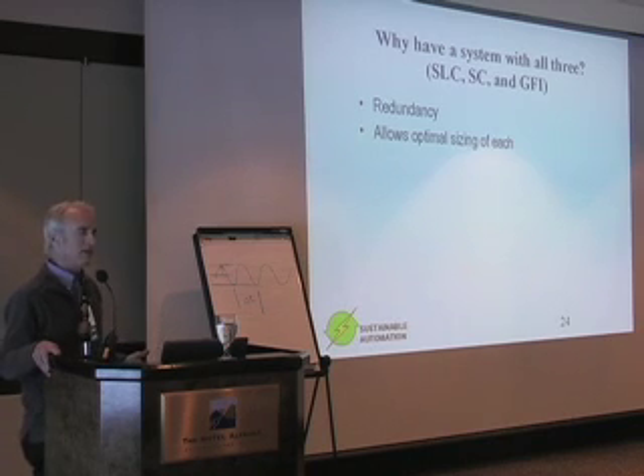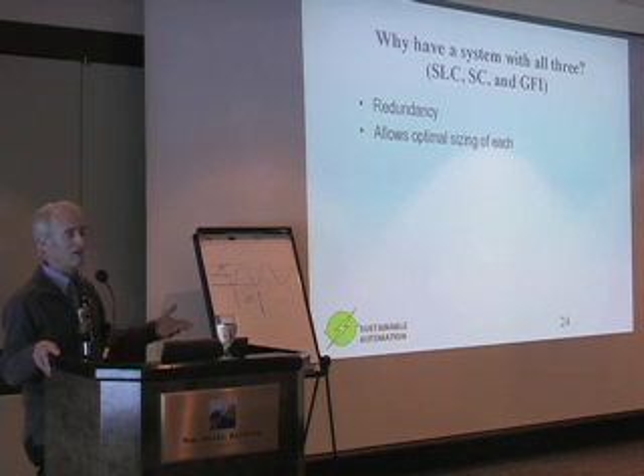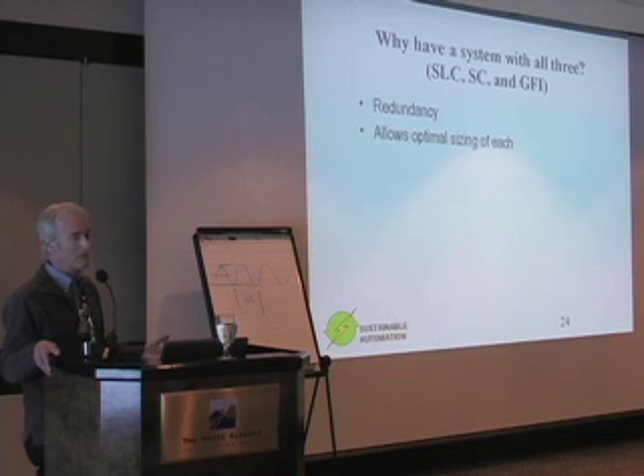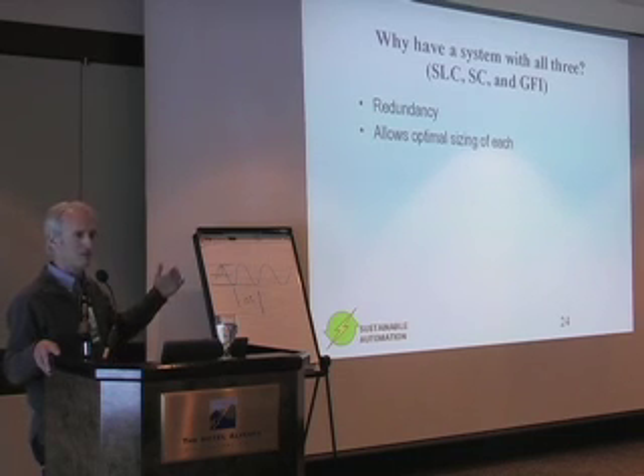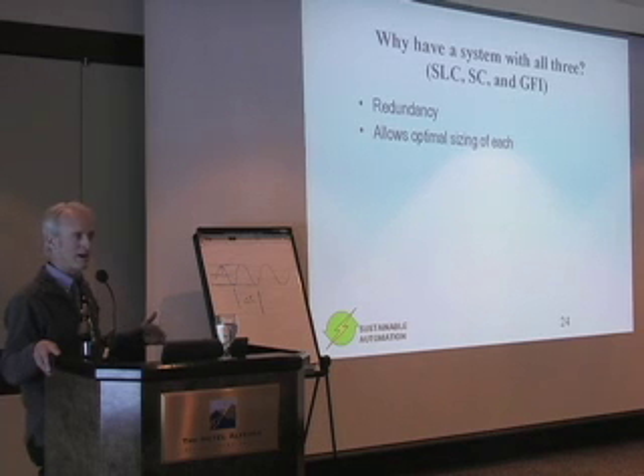Why would you still need a secondary load? Well, if you're talking 15 minutes of energy storage and you're at 150% wind penetration, in other words, you have a 100 kilowatt load and your turbines are putting out 150 kilowatts. Well, you're going to run out of capacity in that energy storage pretty quick. So you still need some place to put excess power to avoid shutting down turbines. Most of these turbines have no mechanism for curtailing their power output, for limiting their power, other than shutting them off.